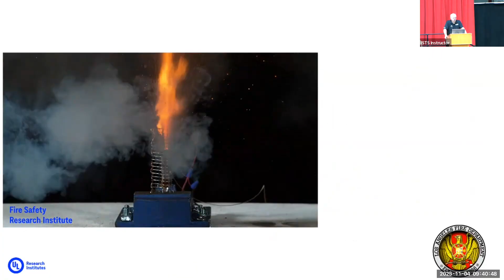What we're looking at here is a single 18650 cell, videoed in slow motion so you can see the gases being released and the jet fire coming off that single cell. That might be something found in a large vape pen or a personal shaver. Then we increase the number of cells so you can see how the fire spreads. These are cells or cell packs that were put into thermal runaway through overheating, where two cells initiated the event, and you can watch the thermal propagation of thermal runaway throughout the pack, getting a sense of the peak heat release rate.